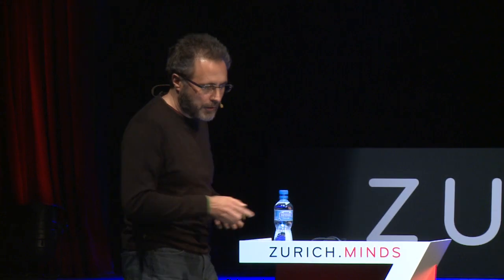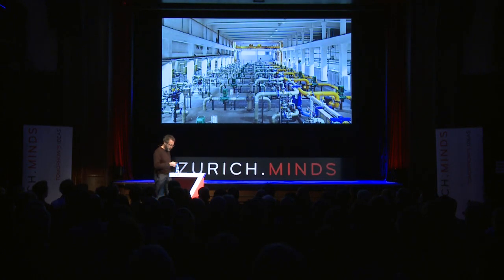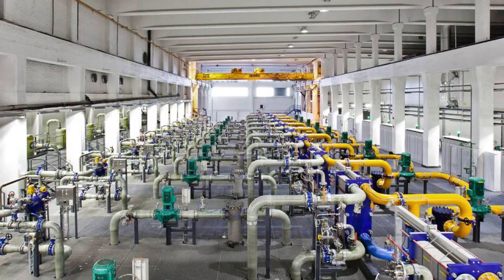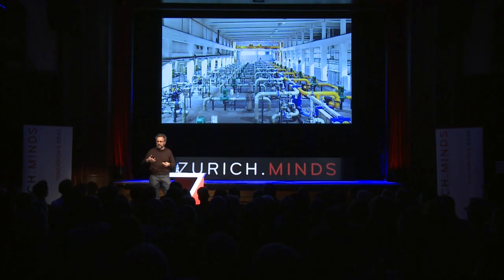It's going through, I have a laser pointer here. It's going through these heat exchangers here. So this is the cold water coming in. It's going through this heat exchanger, and this is the warm water that comes from the floor that was heated up by the servers, and it just exchanges heat in these very simple devices. A bunch of pumps move the water around. Very, very simple system and very, very effective system.